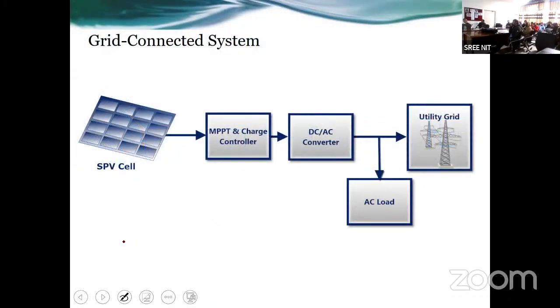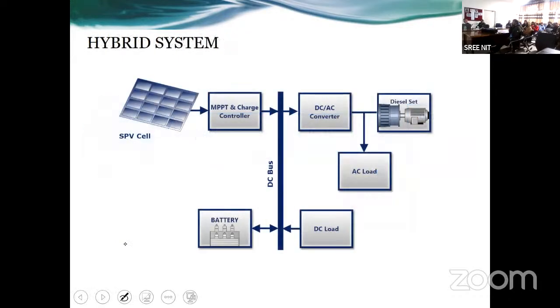Then in a grid connected system, you need to have an MPPT charge controller. So a DC DC converter is going to be there. Then you are having DC AC converters, so you can feed it to the grid, and simultaneously you can also supply it to the AC load connected at the point of common coupling. So hybrid systems, again DC backup, or you can have a diesel set, or you can have a wind turbine also. Hybrid means different combinations of sources meeting the common target to keep on feeding the DC load as well as the AC load, depending on if you are having a DC AC converter also or a DC DC converter also.